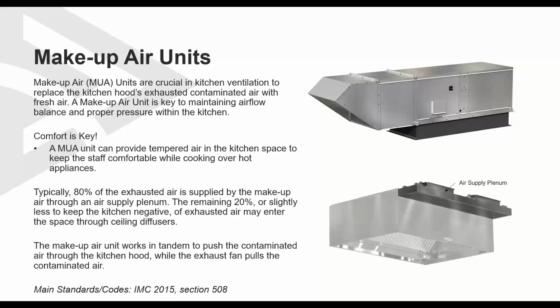The makeup air unit works in tandem to push the contaminated air through the kitchen hood while the exhaust fan pulls the contaminated air. And the main standards and codes that we follow are IMC 2015, section 508.